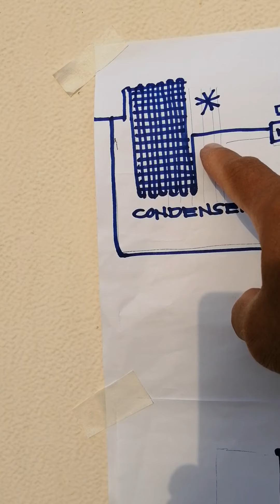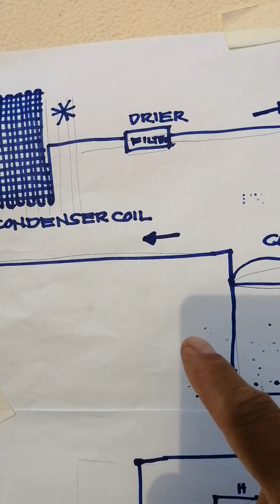The hot air inside the condenser will be thrown out by the fan motor. So now we have a liquid refrigerant. Then it will pass through the filter dryer. The work of the filter dryer is to absorb the moisture and block small particles in the system, to keep the compressor from being damaged. Okay, now our liquid passes the dryer and then enters the capillary coil or tube.